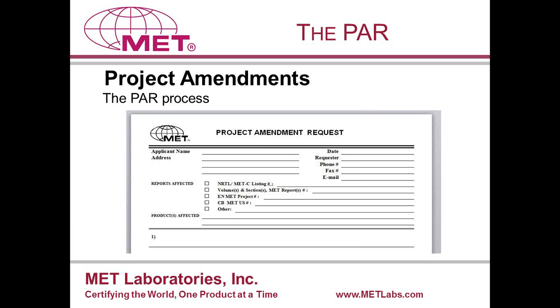It's also worth mentioning that if your product requires production line testing for dielectric strength and/or ground continuity, the equipment you use to perform those tests requires annual calibration. If you don't keep up the calibration programs, you could wind up not being able to mark your product until the calibration is performed.